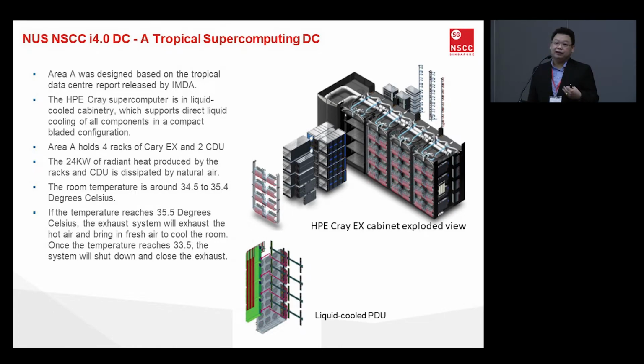Okay, of course, in the event that the temperature goes higher, we do have a series of systems to help us reduce the temperature. All right, so in the event that the room temperature hits 35.5, we have an exhaust system that will kick in. All right, this exhaust system will start drawing in cold air from outside. Okay, typical Singapore temperature is about 26 degrees, all the way to, on a hot day, 35 degrees. All right, so in the worst case scenario, 35 degrees, we're still pulling in cooler air, because the room is 35.5, right? So we pull in the cooler air from outside, and exhaust the hot air out into the environment. All right, so this will go on until the temperature in the room drops all the way to 33.5. That's where the exhaust system will close.